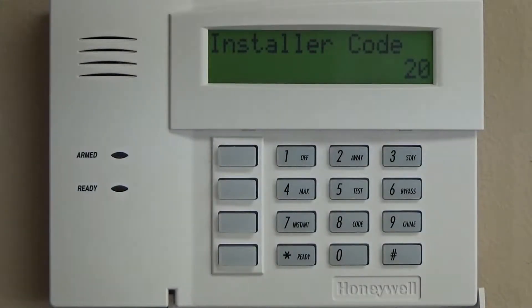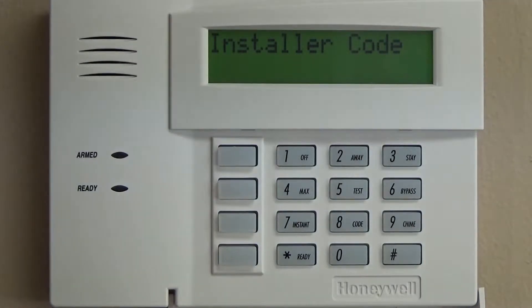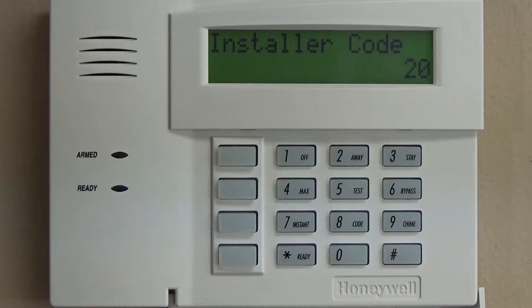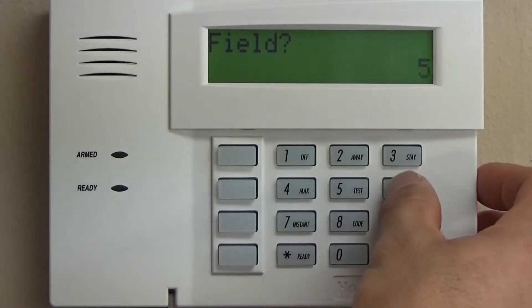The first thing we are going to do here is we are going to program zones 1 through 8. There's some other programming that we're going to skip past, but by programming zones 1 through 8 as no response, that will simplify the programming process so that as we enter and exit programming, you're not going to have to worry about trouble beeps, fire alarms triggering, and that type of stuff. To enter the zone programming, we're going to go to star 5, 6.